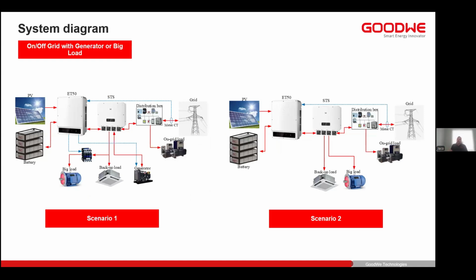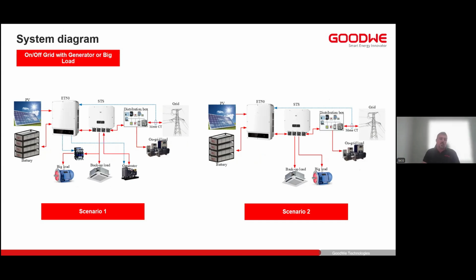There are two system operational methods with the generator port. So scenario one is with the direct generator integration. The generator will then be connected to the generator port and connected to the inverter that will receive the start and stop commands. Alternatively, that same port can be used as a big load output port. And there are various settings and conditions that can be linked to that port. So it can be based on a time schedule, based on SOC of the battery, based on PV production, or it can be a priority load as well.